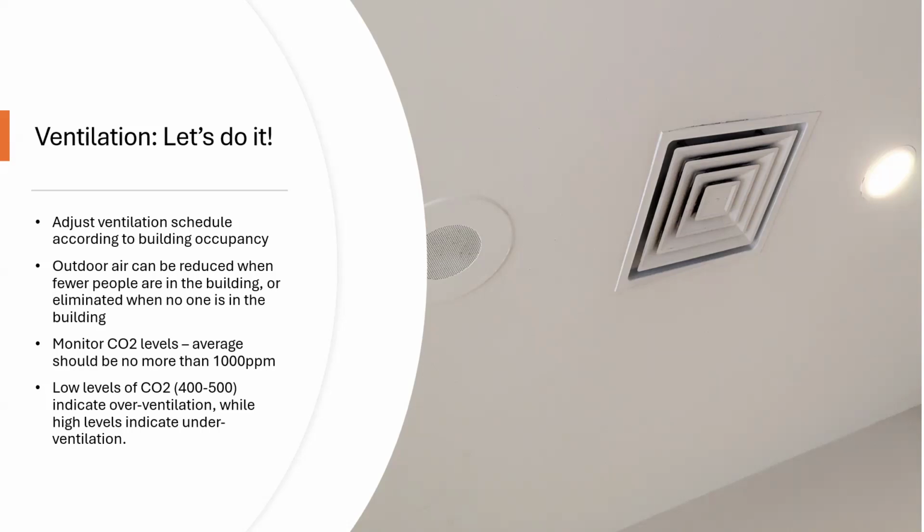I've actually been doing it. I got the CO2 monitor last week for Greenup, and I've been keeping track. I made some adjustments to our ventilation system, because we were getting very low CO2 readings between 400 and 500. So I lowered the ventilation rate a little bit. Now they're up between 600 and 700, and the humidity has gone up as well, because it measures the humidity. That's a good outcome, because it hasn't gone up too high. It's still only about 30%, which should be even higher for comfort, but it's a good outcome. It's more comfortable, and we should be saving energy as well. It's kind of a fun thing to do if you're into that. I recommend it. Use your library card.